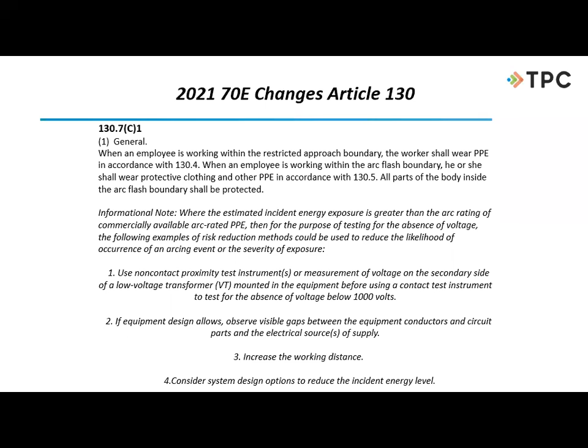Increasing the work distance is always something we should look at to try to keep workers safe. And then the design of the equipment, somehow to put in something that could reduce that incident energy, either zone selective interlocking, class L fuses, maintenance mode button on circuit breakers, something that could help us get that down a little bit.